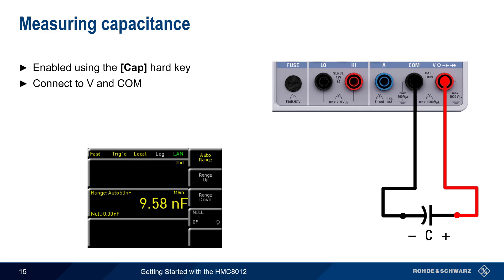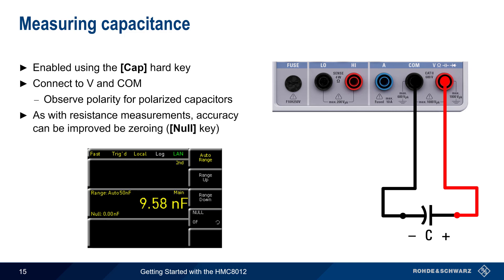Capacitance measurements are enabled using the CAP hard key. Connections to the capacitor under test are made using the V and COM jacks, and results are displayed in units of farads. Be sure to observe the polarity when measuring polarized capacitors. As with resistance measurements, capacitor measurement accuracy can be improved by zeroing – that is, by shorting the leads and pressing the NULL hard key before making measurements.